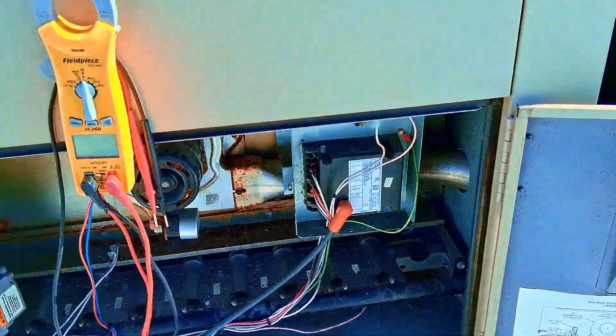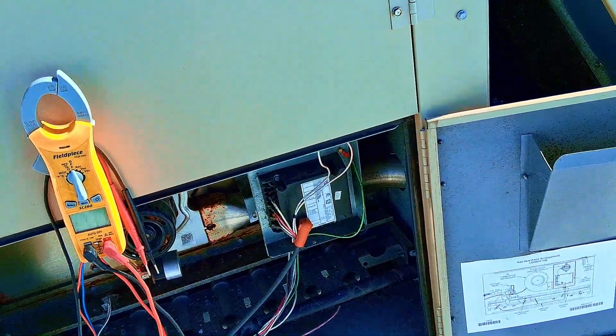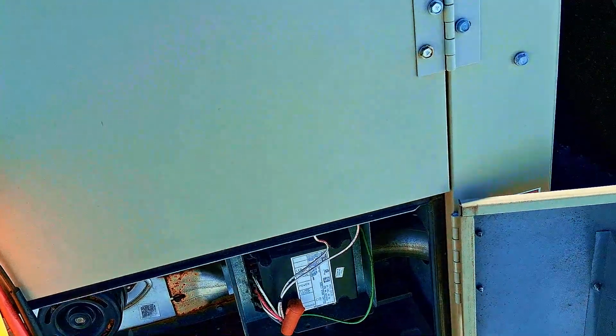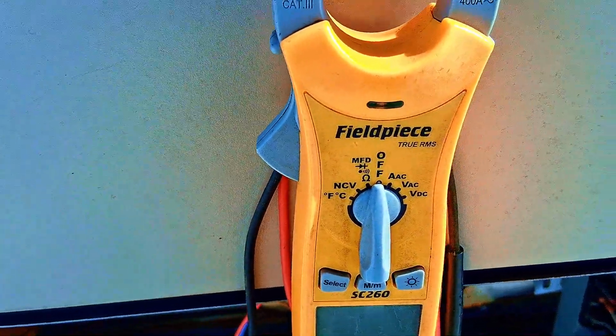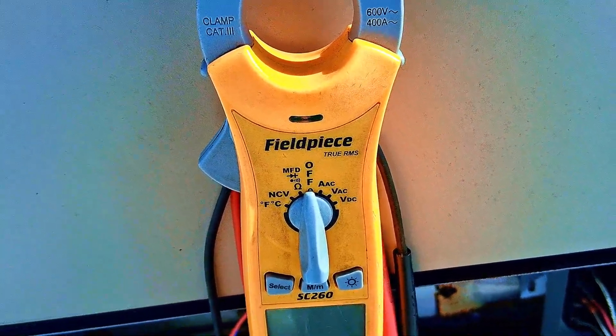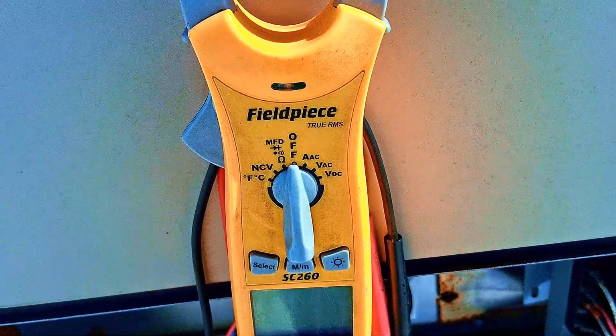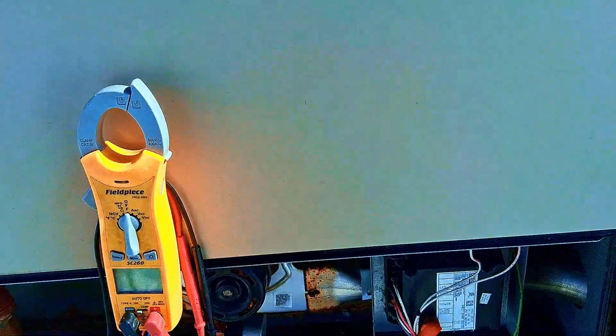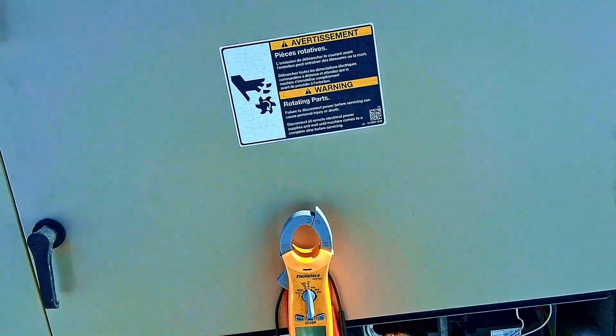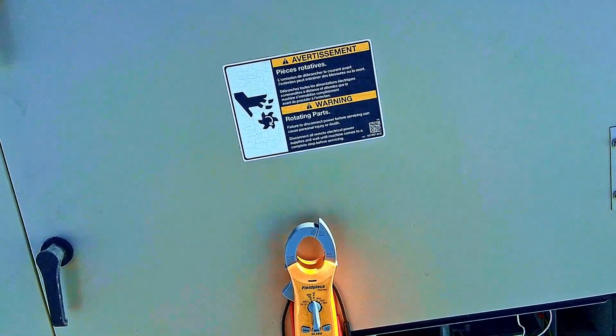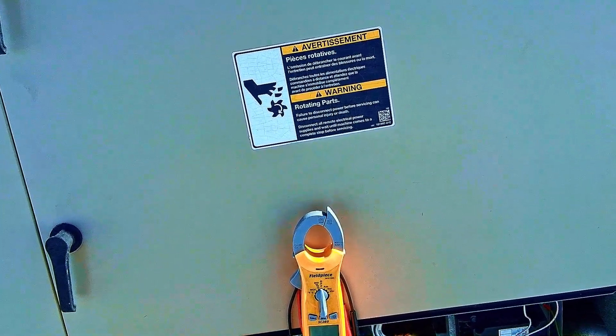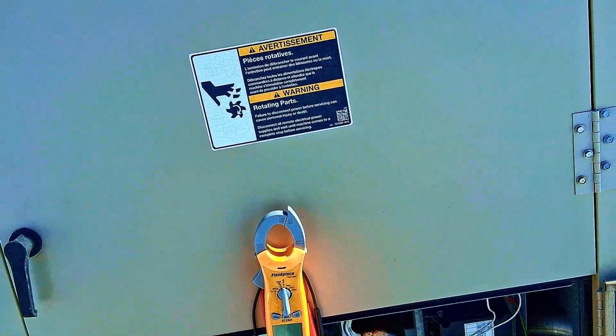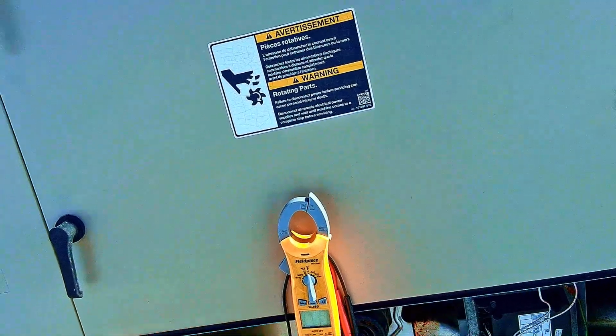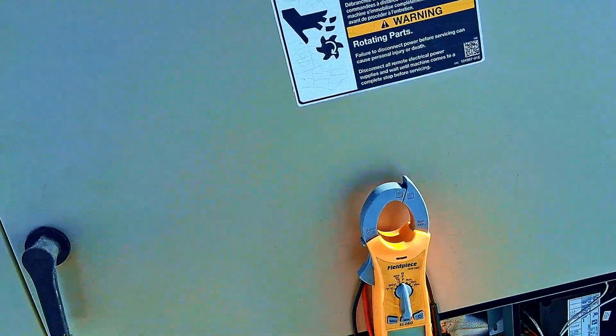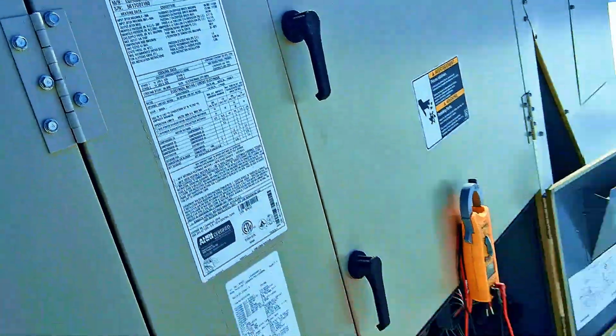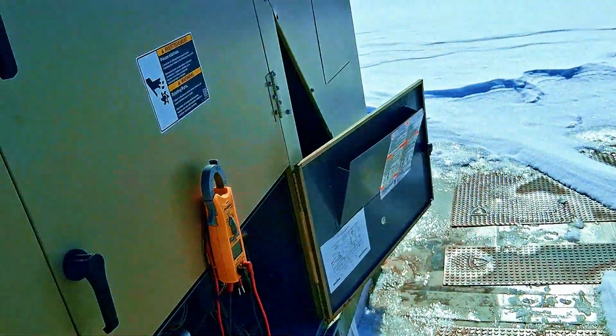Alright, so I cleaned my flame sensor, put it back on there. I can't really take the flame rectification reading because the meter I have right here doesn't have the amps DC option to read the amperage that it sends out. So we're just gonna turn it on with that cleaned and see if it stops giving an alarm code in terms of gas valve proving.